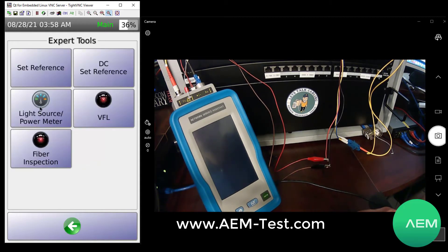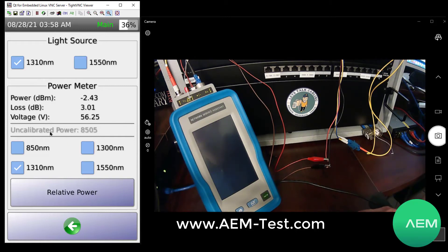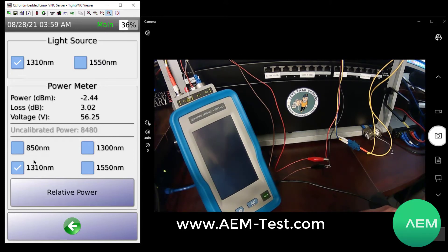You've also got standalone light source and power meter mode. In that mode, we can actually measure the absolute power coming from the far end, and we can also see the voltage if the voltage is hooked up. We can do this at both 1310 and 1550. This can be set up as just a light source or just a power meter as well — so if you have a secondary light source on the far end or want to measure absolute power coming from equipment, you can do that.